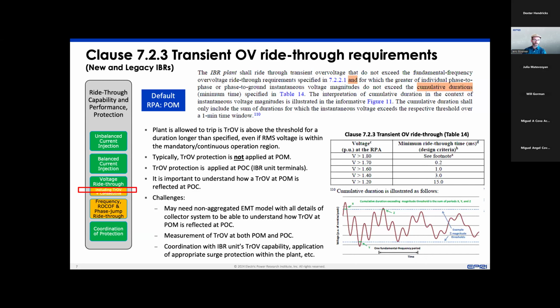It is also important to understand how a transient overvoltage at the POM would translate to transient overvoltages at the POC. If you do have surge arresters or similar things in the plant, some of them may clip parts of that overvoltage. So you do not necessarily have to set your IBR unit transient overvoltage protection at the highest value of what's specified in IEEE 2800. We have tested some inverters and know that they are capable of riding through transient overvoltage up to 1.5 per unit, for example.